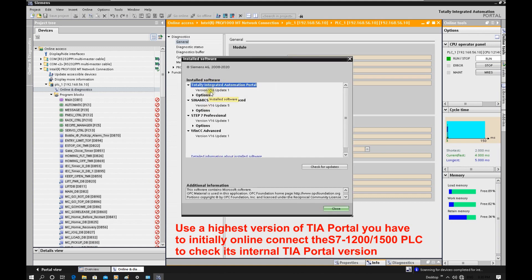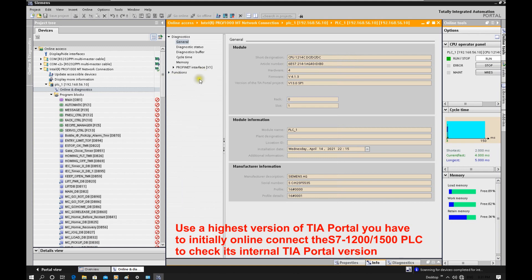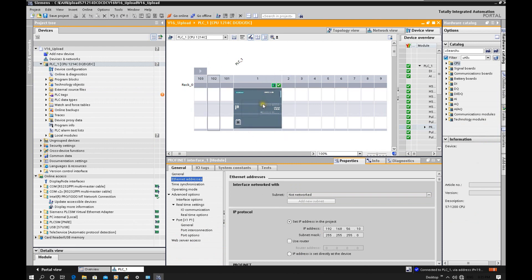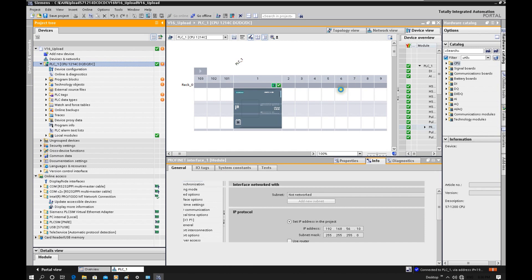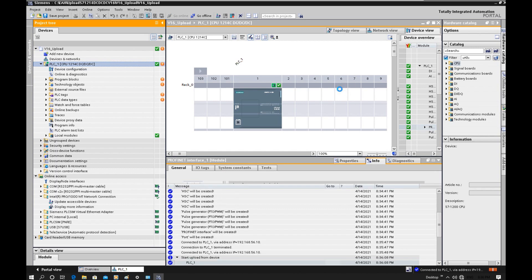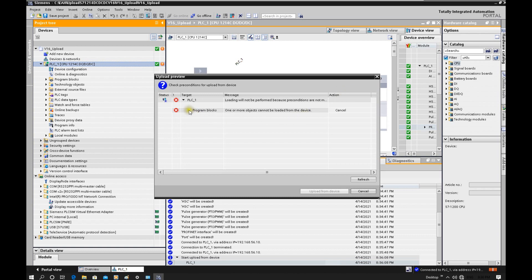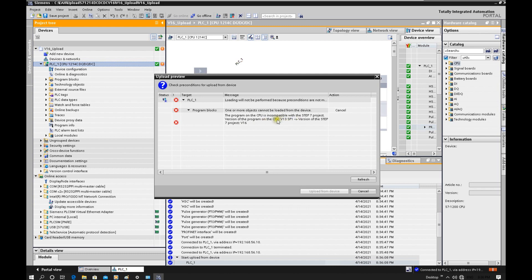Currently I am using version 16. If I create a new project and try to upload, let's see what happens. We go online with the CPU, then click Project and click Upload from device. Here is the problem — because I am using version 16, but the CPU was programmed with TIA Portal version 13. So even using the higher version, it doesn't work. We have to use the matched version to upload this CPU.